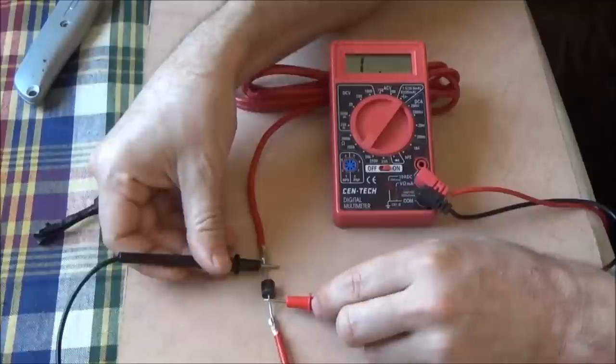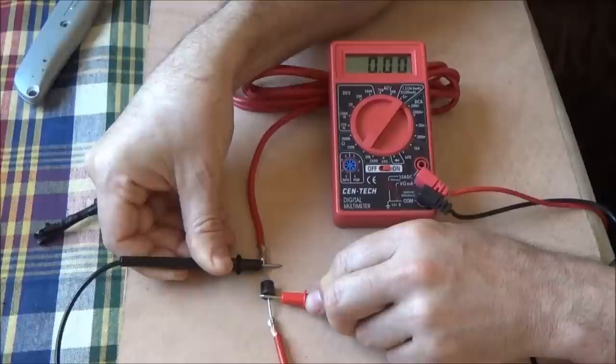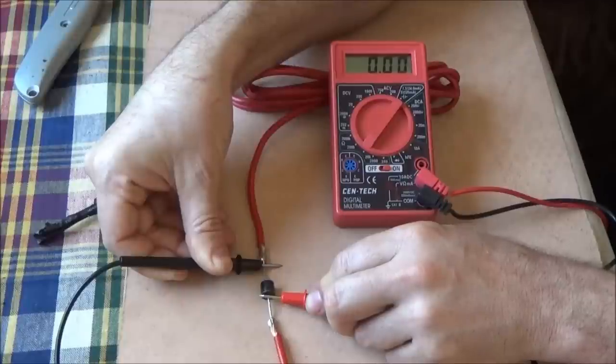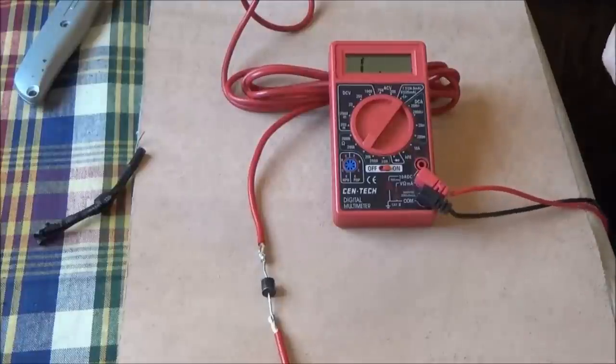Now if we try it in the other direction, what do we see here? Look at that, 0.01. So this diode shorted out. It was an absolute dead short, completely dead short, and acted like a piece of wire.